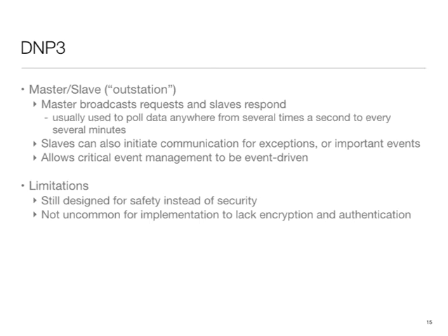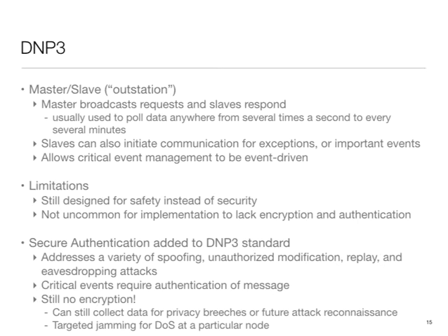Now, the latest DNP3 standards, for example, do have authentication. Authentication basically refers to whether we can validate that this is the device or the user which claims to be it, so that you can prevent spoofing attacks and those kinds of things. They still do not have encryption, so there is no confidentiality. Now, you might imagine that in this kind of setting, perhaps confidentiality is not important. But people have also shown that there are lots of attacks which can leverage the lack of confidentiality.